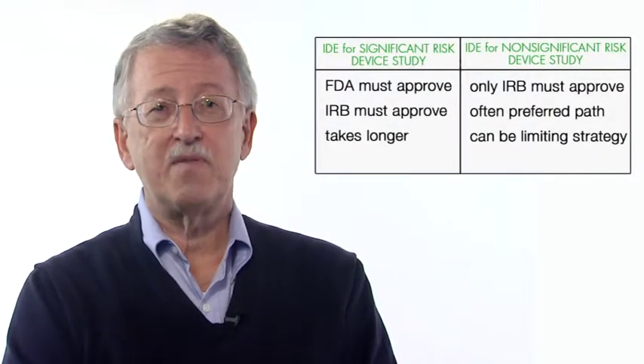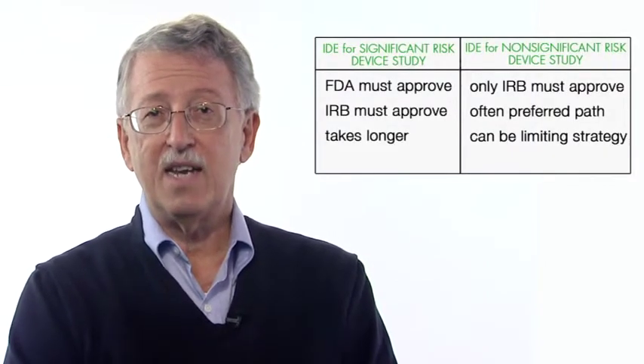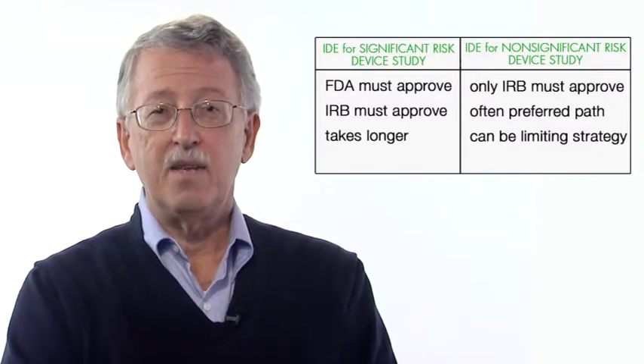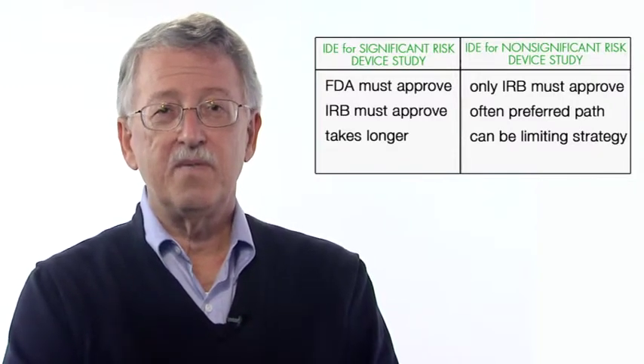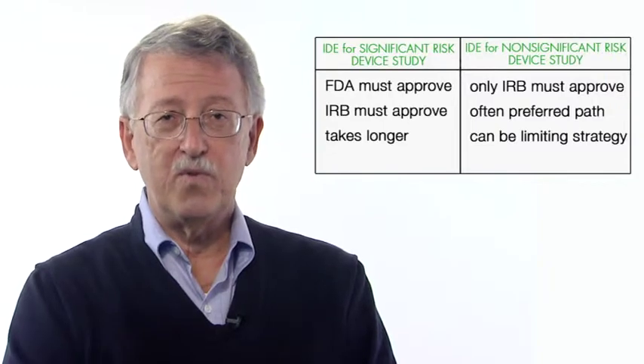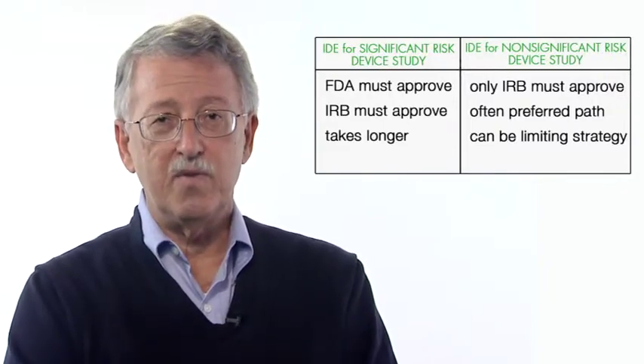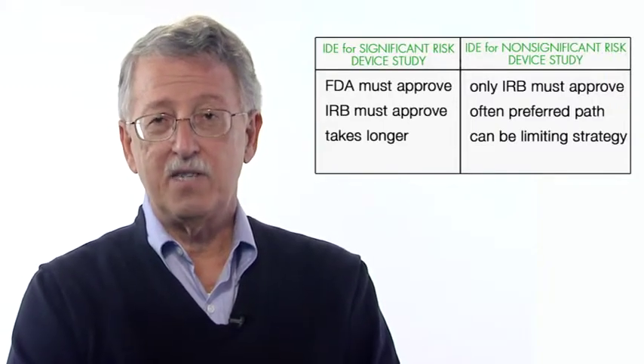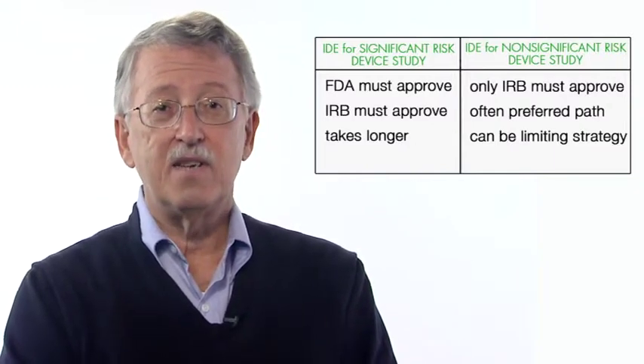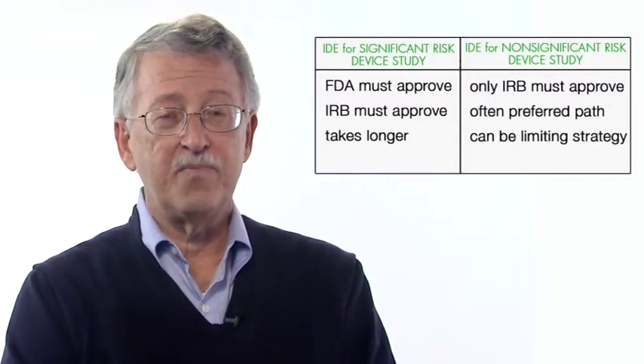Importantly, there are two types of IDEs: a significant risk IDE and a non-significant risk IDE. The principal difference is that significant risk devices must be approved by FDA and by an institutional review board at the hospital where the study will be conducted. Non-significant risk devices only require IRB approval.